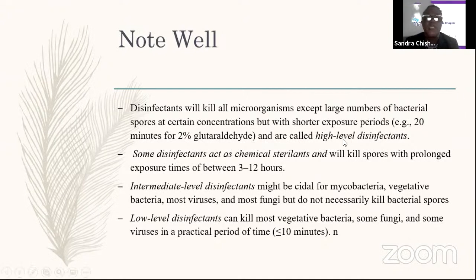However, there is a point that I want you to note. Disinfectants will kill all microorganisms except large numbers of bacterial spores at certain concentrations, but with shorter exposure time. For example, 20 minutes for 2% glutaraldehyde, and these are called high-level disinfectants. Some disinfectants act as chemical sterilants and will kill spores with prolonged exposure. So your glutaraldehyde with prolonged exposure is no longer a high-level disinfectant. It becomes a chemical sterilant.